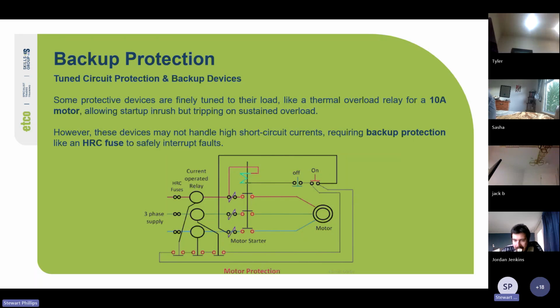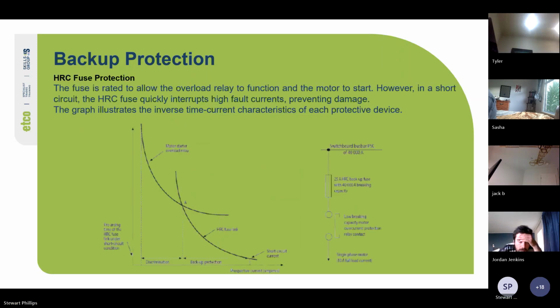A thermal overload can handle overloads, but it takes a while to act. So if there's a large current spike due to a short circuit, we need those HRC fuses to help disconnect the supply. Cool. So, HRC fuse protection. The fuse is rated to allow the overload relay to function and the motor to start. However, in a short circuit, the HRC fuse quickly interrupts high fault currents, preventing damage.